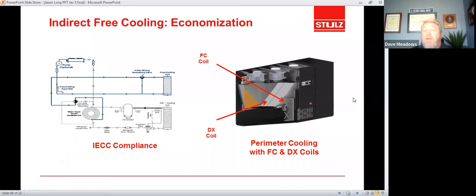The next thing I'd like to talk about is indirect free cooling or economization. Now, the free cooling units are designed specifically to provide for compressor-free cooling during those months of the year where it is cold enough outside to cool the glycol solution that is used for the condenser, such that it can provide the cooling to the data center. So there's 2 coils in there, and what you're seeing is a cutaway of an upflow free cooling unit. So the air would be coming from the white space, the data center or computer room, coming through the front of the unit, hitting that free cooling coil first. And if it's cold enough outside, we would direct the cold glycol solution through that coil to begin removing heat from the space.